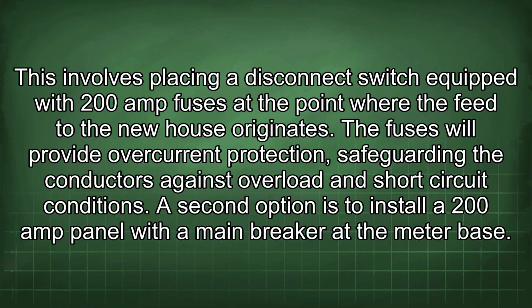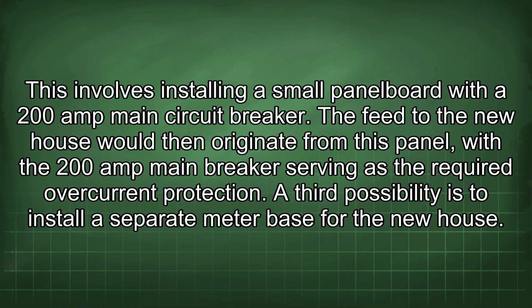A second option is to install a 200 amp panel with a main breaker at the meter base. This involves installing a small panel board with a 200 amp main circuit breaker. The feed to the new house would then originate from this panel, with the 200 amp main breaker serving as the required overcurrent protection. A third possibility is to install a separate meter base for the new house.